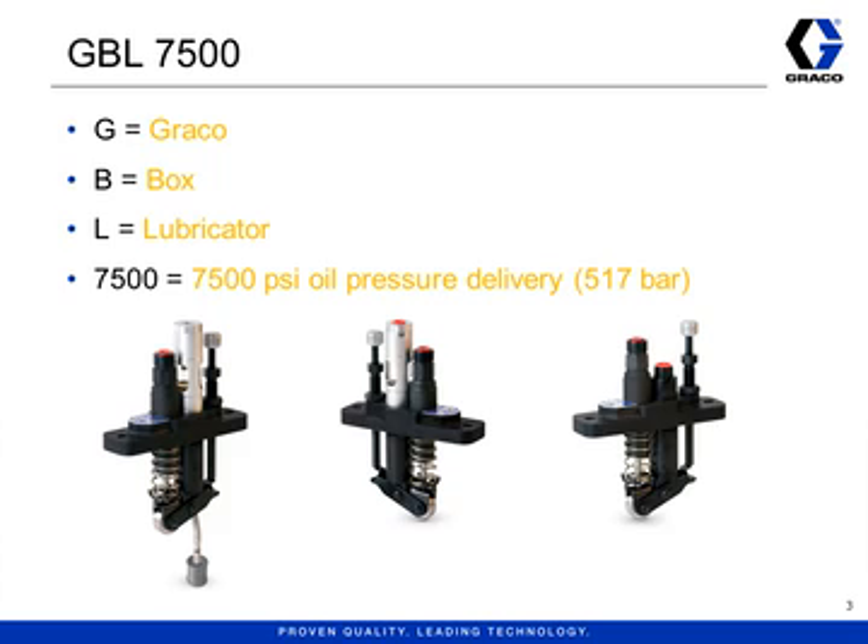The pumps used with the GBL are collectively named GBL 7500. These pumps were designed to replace several older pumps and also designed to fit into the reservoirs made by our competitors. The pumps used in box lubricators are piston pumps and the stroke of the piston is powered by a camshaft. Each pump sits on top of a single lobe cam, so every rotation of the camshaft results in one stroke of the piston.